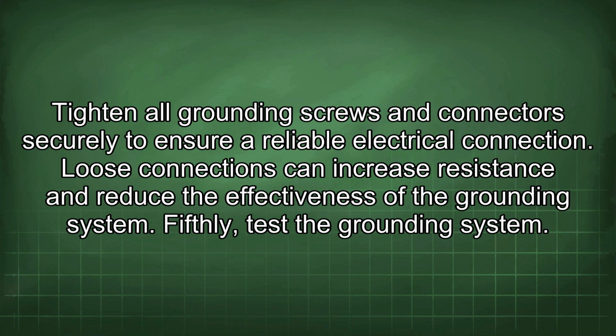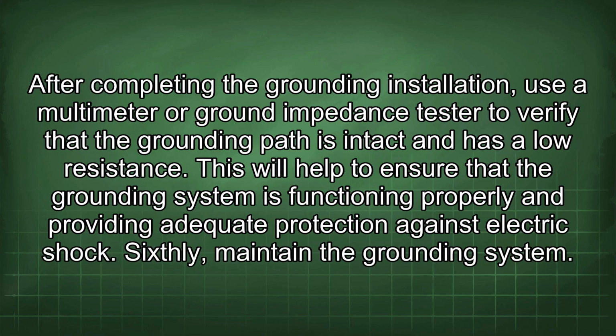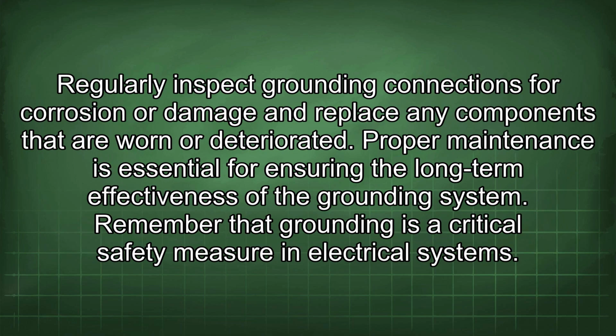Fifthly, test the grounding system. After completing the grounding installation, use a multimeter or ground impedance tester to verify that the grounding path is intact and has a low resistance. This will help to ensure that the grounding system is functioning properly and providing adequate protection against electric shock. Sixthly, maintain the grounding system. Regularly inspect grounding connections for corrosion or damage and replace any components that are worn or deteriorated. Proper maintenance is essential for ensuring the long-term effectiveness of the grounding system.